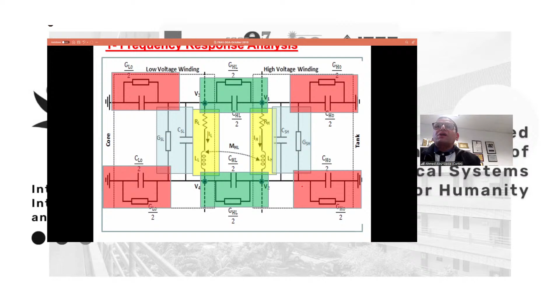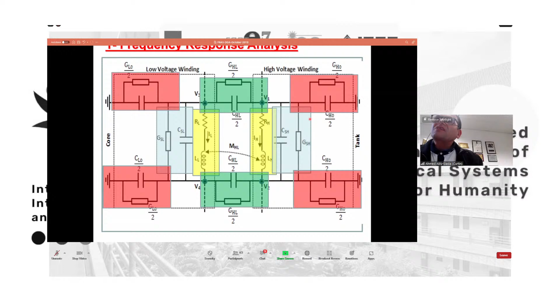Okay? Frequency response analysis came from this equivalent circuit. We have a capacitive component, we have an inductive component, which are frequency dependent. Remember, XL equals omega L, XC equals 1 over omega C. So any variation in the transformer winding, whether the winding is moving up, down, to the right-hand side, or the left-hand side, due to any reason that I will explain later, will affect the capacitance and the mutual and self-inductance, right? For example, refer to the basic formula for capacitance, epsilon A over D. If you change the distance between two turns, that will change the capacitance. And that will affect the frequency spectrum of the transformer. That's what we call the frequency response analysis signature.